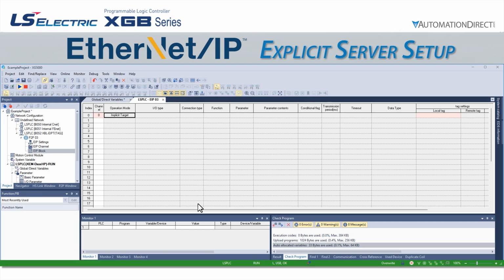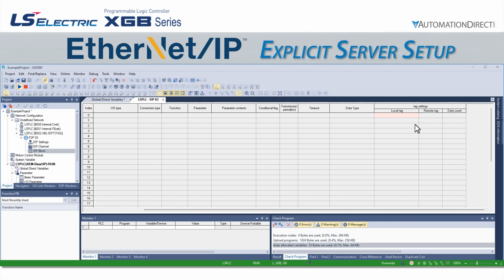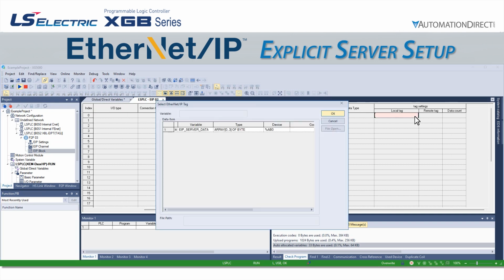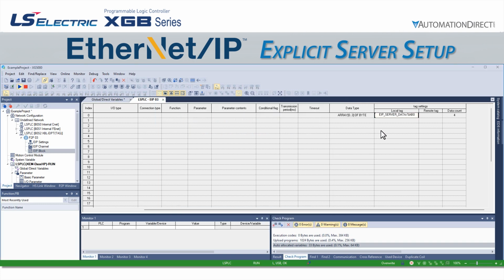The only remaining field to be configured is the local tag field. If we double-click here, it will open a new pop-up window showing us all available variables that have had the EIP OPC UA box checked. In our case, it is just the array we created. When we select it, the software adds it to the local tag location. Once we write this project to the PLC, we will be able to access this information from an explicit client.